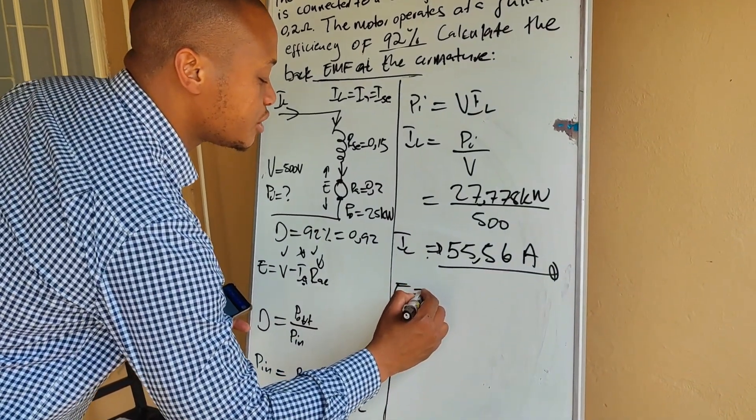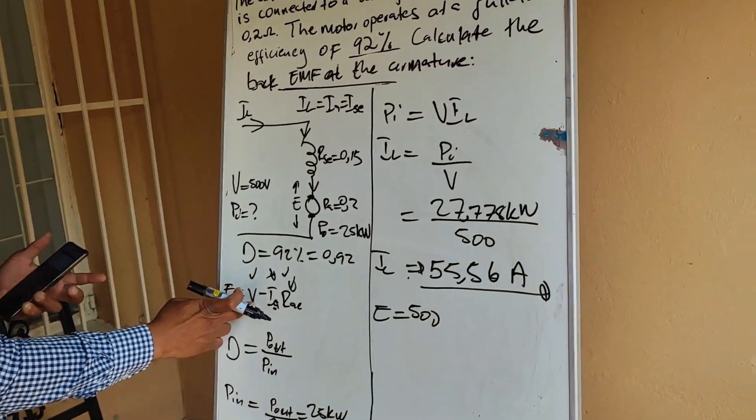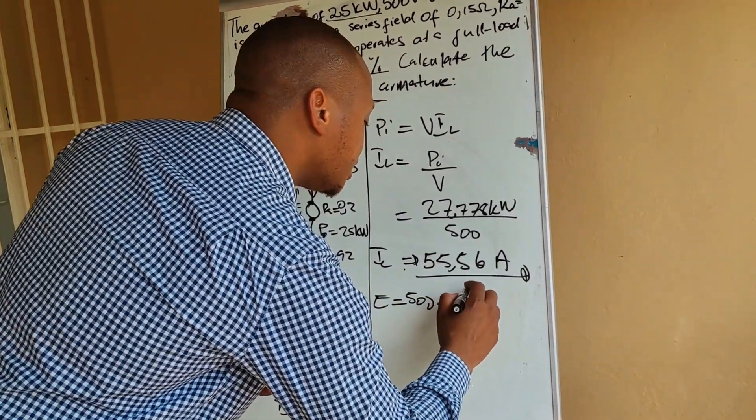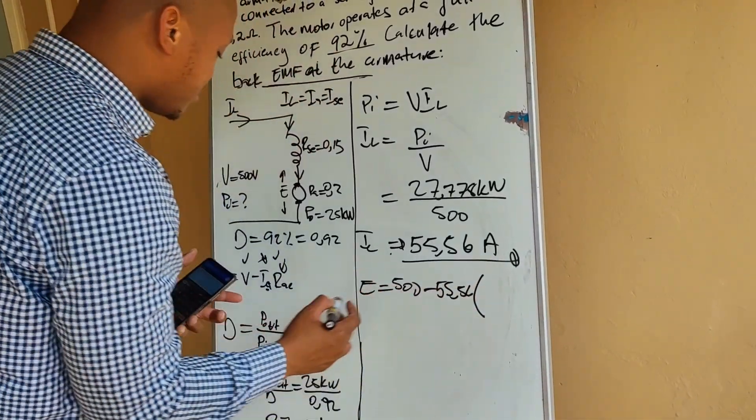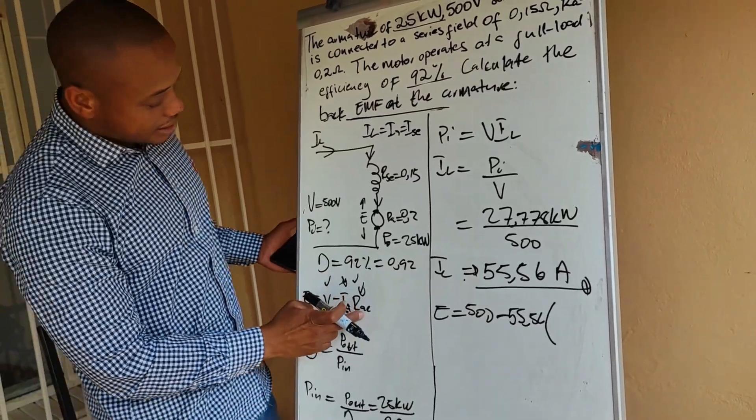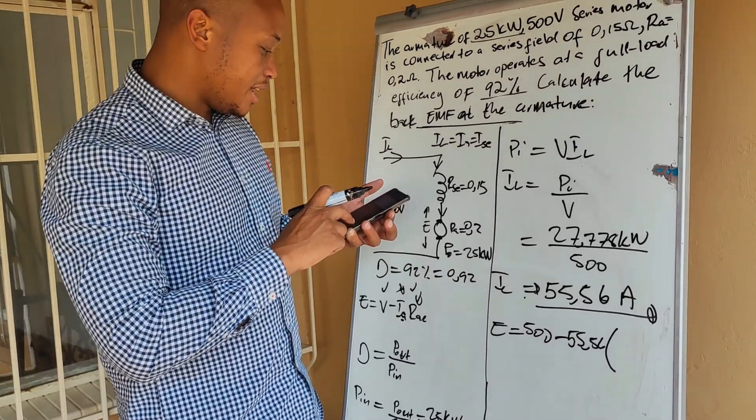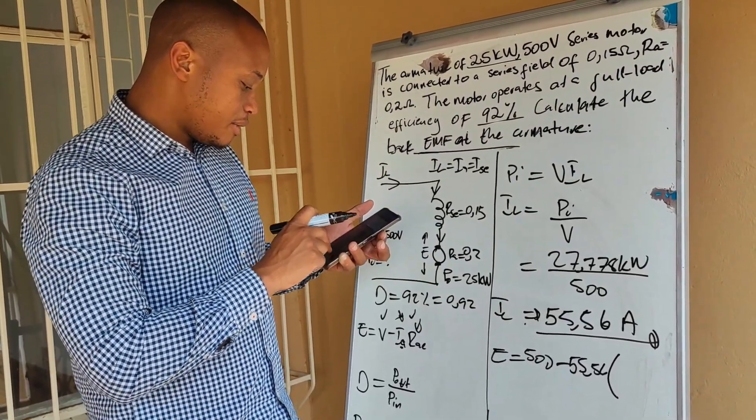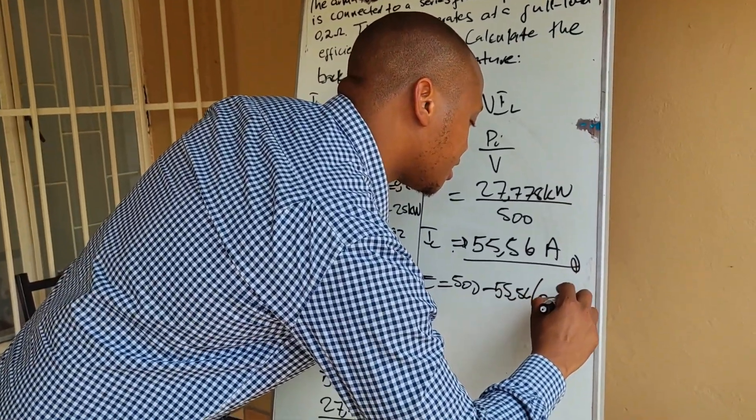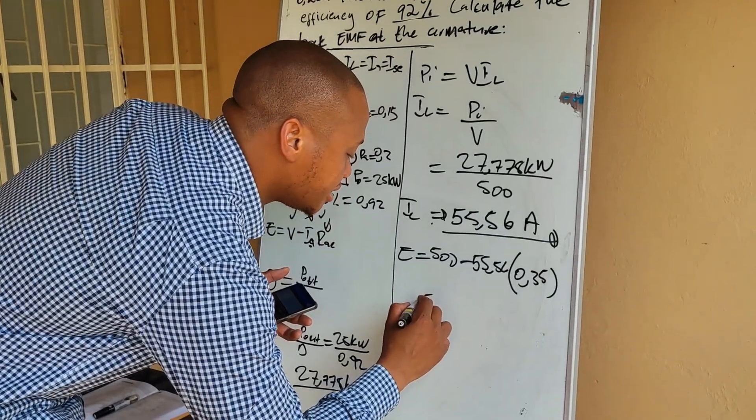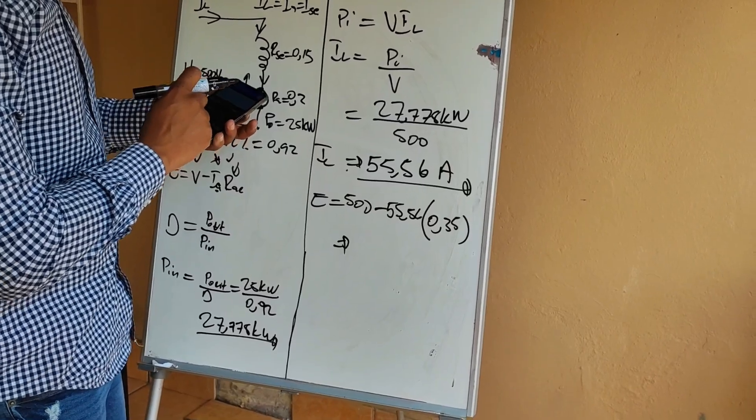So now to calculate the back EMF we say E is equal to V which is 500 minus IA which we calculated as 55.56 multiplied by RAC. RAC is a combination of RSE plus RA. If we add those two together it's 0.15 plus 0.2 which gives you 0.35. And the back EMF will then be equal to 480.55 volts. So that is the value of the back EMF.